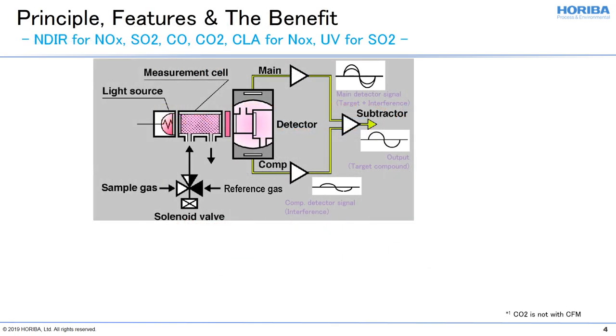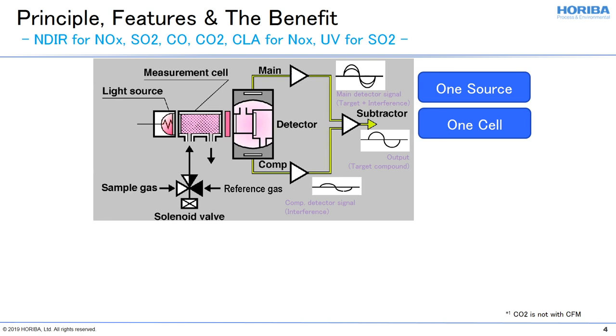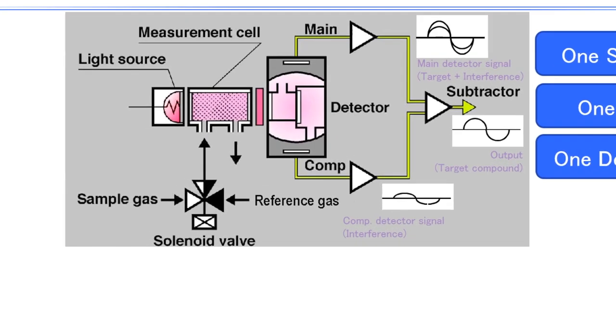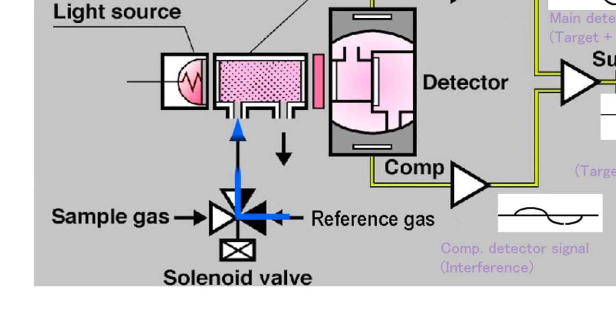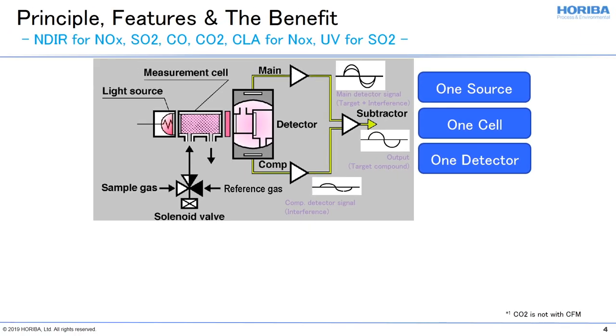Horiba's patented cross-flow modulation uses one light source, one cell, and one detector. A solenoid valve selects alternate sample flow and reference gas flow every half second, resulting in the flow path shown: reference gas, then sample gas, then reference gas. The detector reads reference gas as zero and then reads sample gas as span.